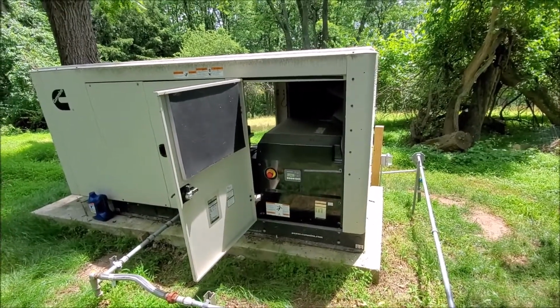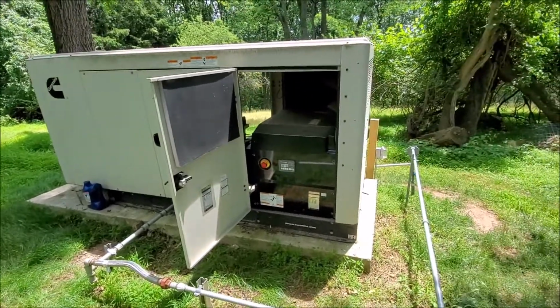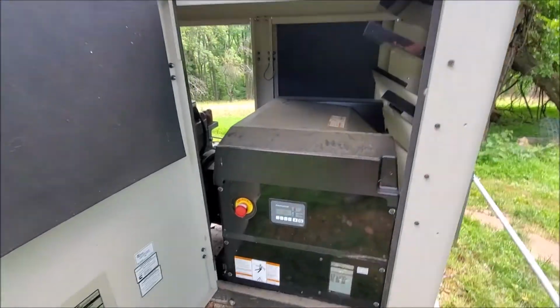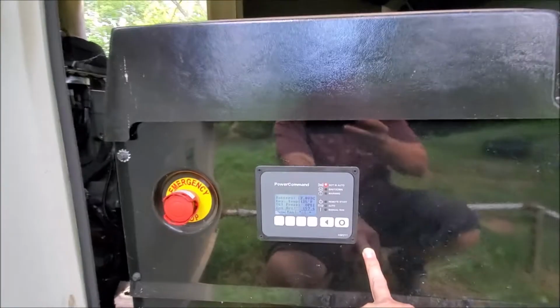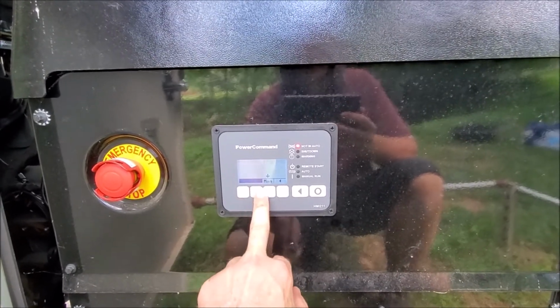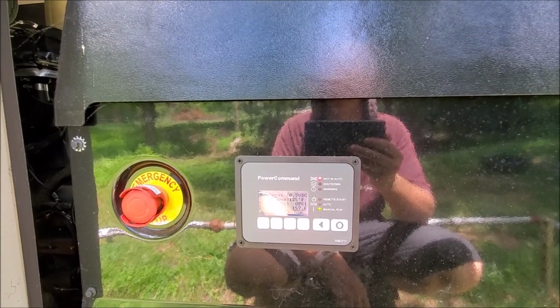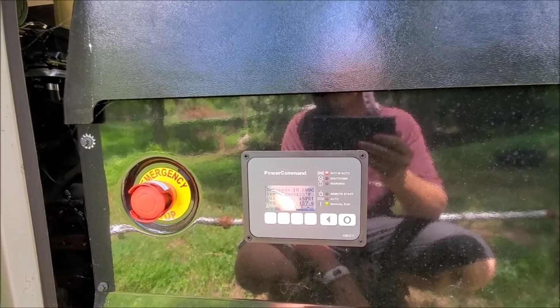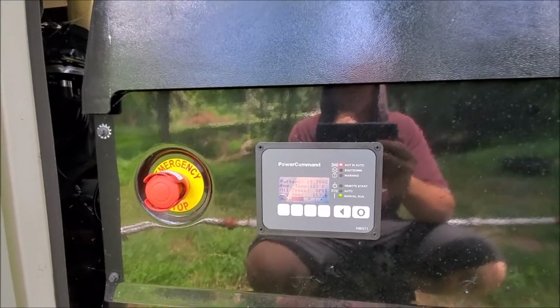Alright, so I put about 3.5 containers, those little containers over there, in. The dipstick now saying full, so anyway, I just pulled the emergency plug out. It says ECM data save in progress. As soon as that is completed, which it is now, it says not in auto. You can hit auto or you can hit manual. I'm going to give it a quick test start and then check it out. Well, it'll have another crack in a minute.